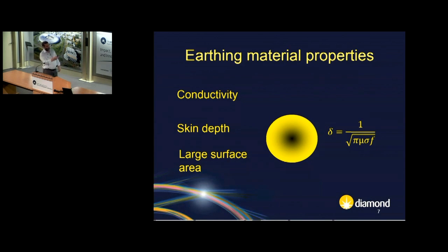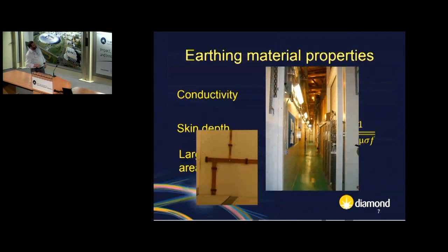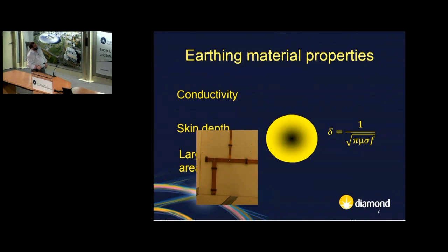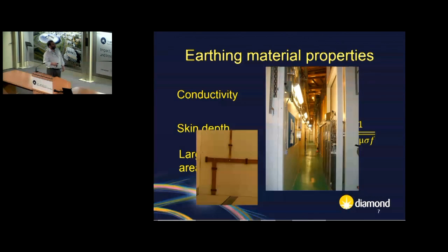So we like that - that tells us copper's quite good. It's not magnetic. Steel is not a very good conductor, and when we take into account the magnetic permeability, it's even worse. However, we do use large surface areas. The copper earthing bars are in the form of these tapes, and we've got lots of steel. It may not be a very good conductor, but we've got an awful lot of it, and connected together it provides quite a good earthing plane.